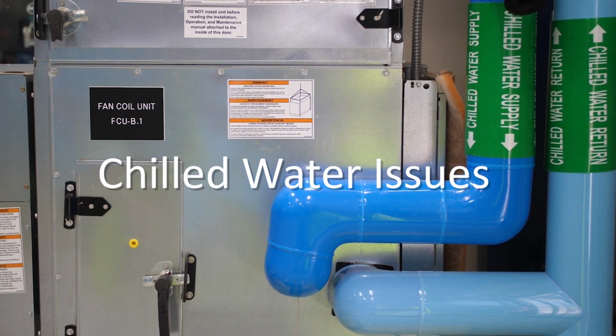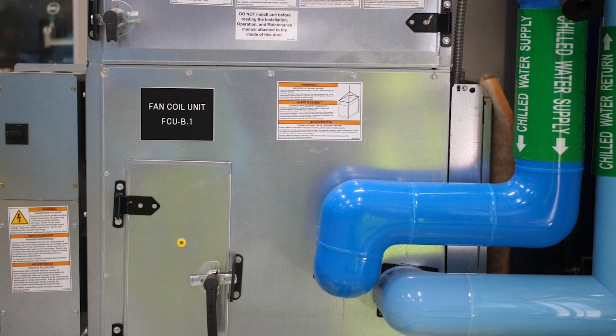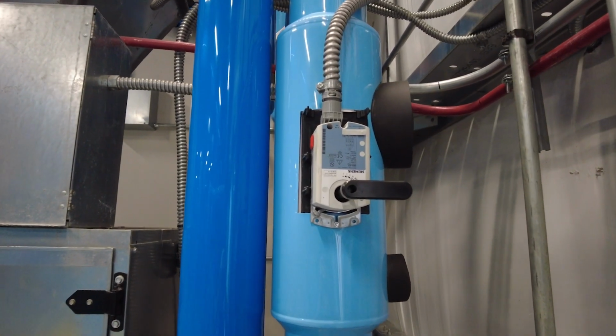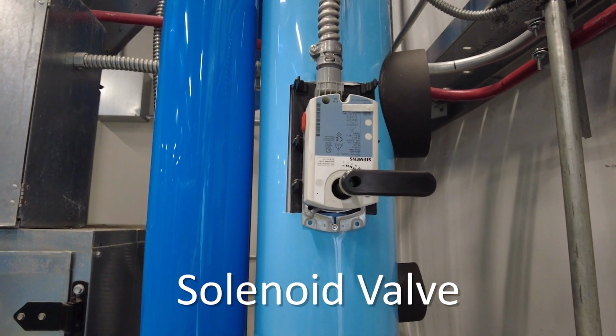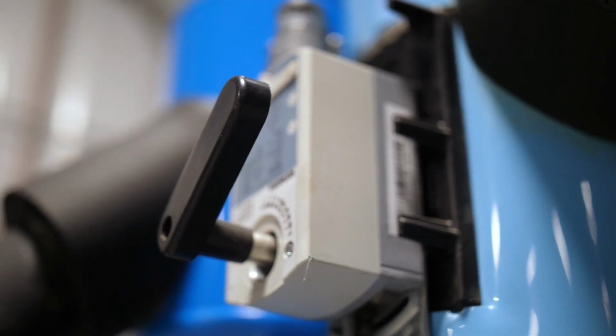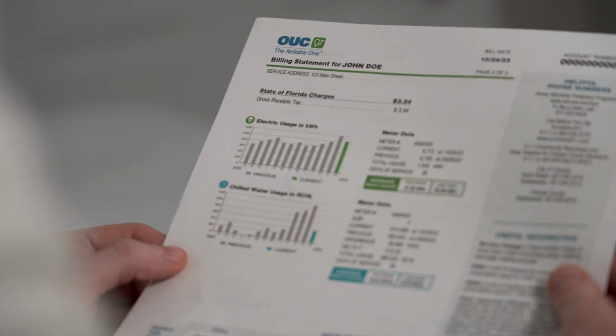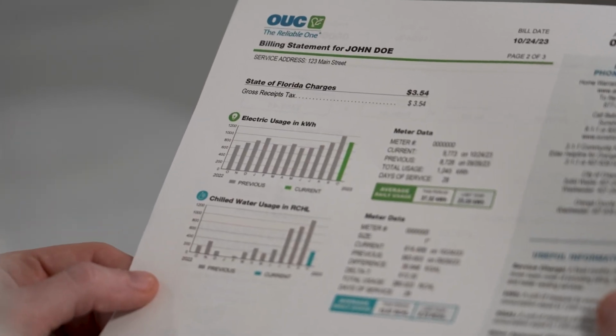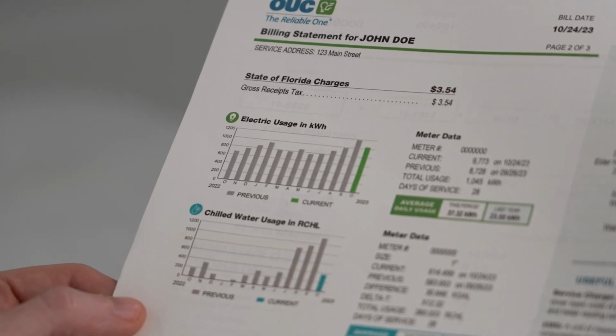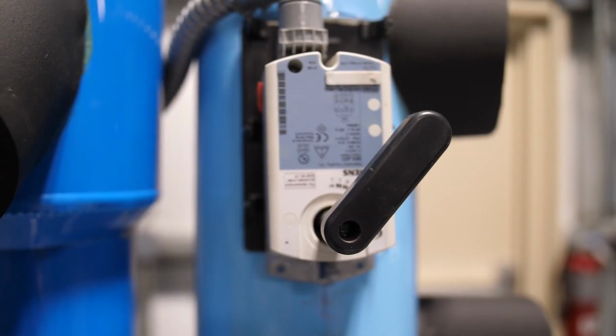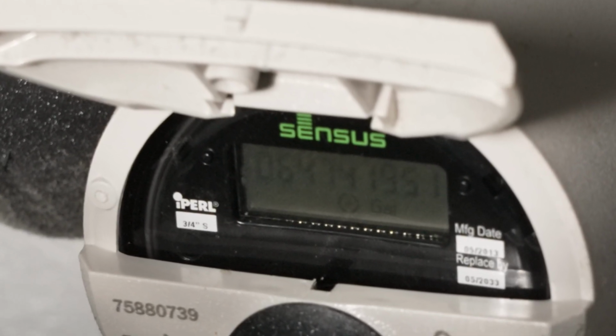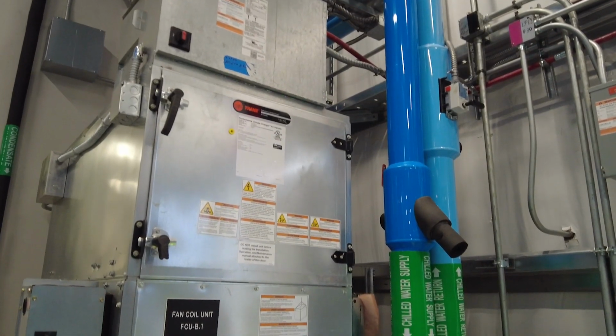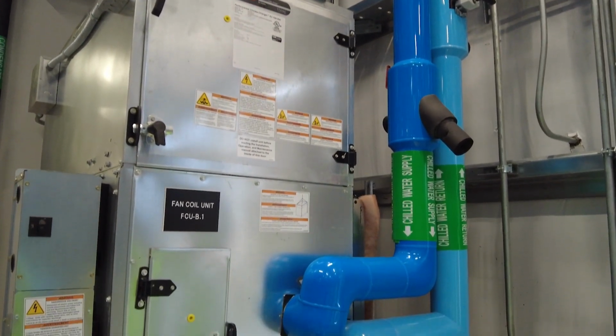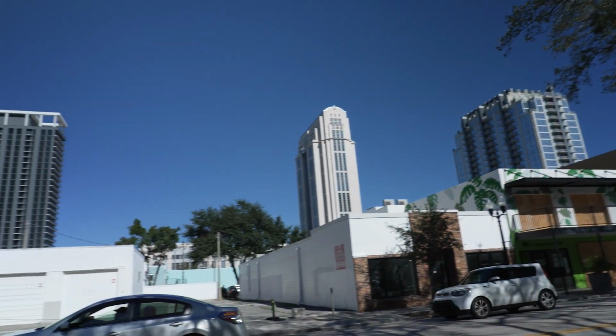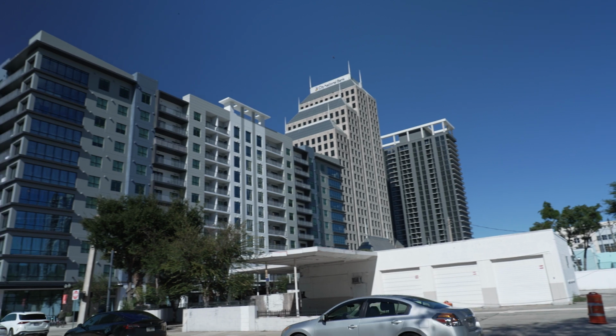Now let's see what can cause problems on the chilled water side. In most cases, the main culprit of a high chilled water bill is the solenoid valve. This valve opens and closes many times a day and can wear out quickly. If it's stuck open, chilled water continues to flow even when the unit is switched off. Since you are billed for every gallon of chilled water used, it's critical that this valve is working properly. You can always verify the flow by watching the chilled water meter for a minute or two. If you suspect something is amiss, it's best to leave it to a professional, either your building engineer if you rent or lease, or your chosen HVAC company if you own your unit.